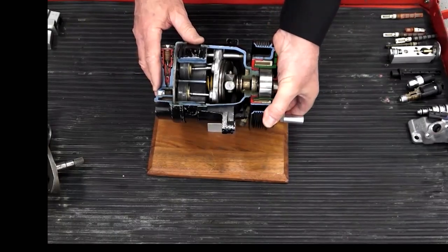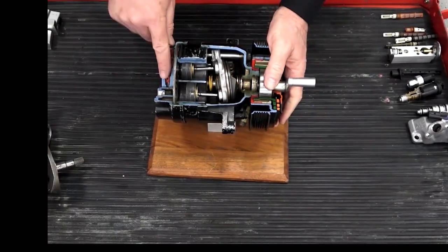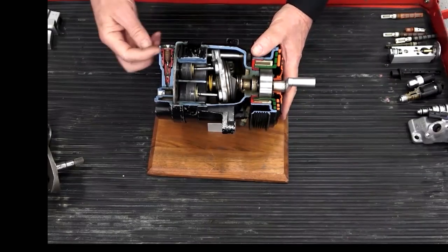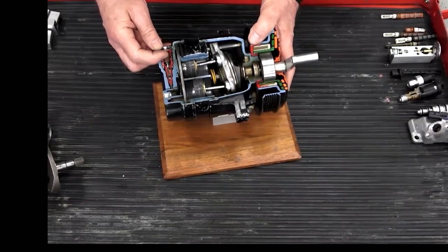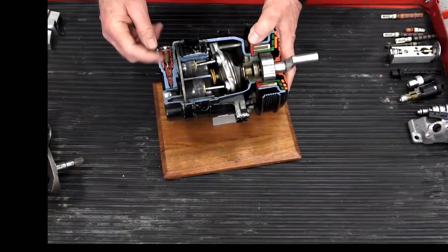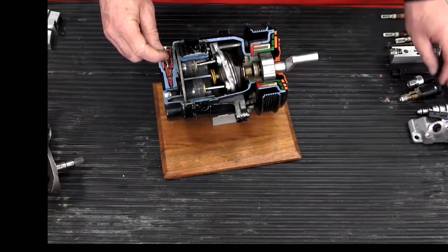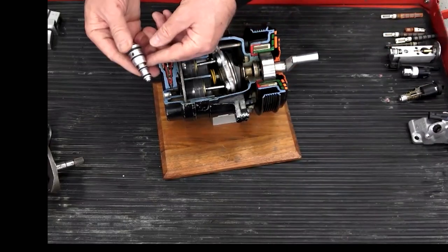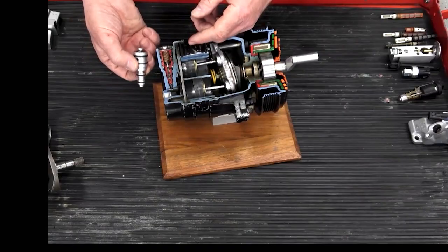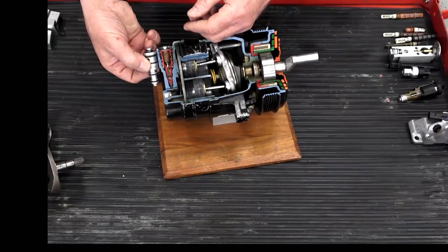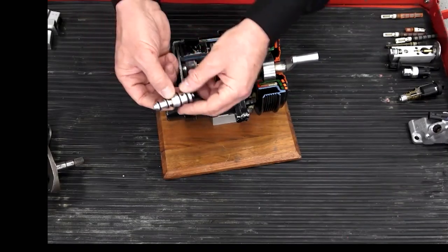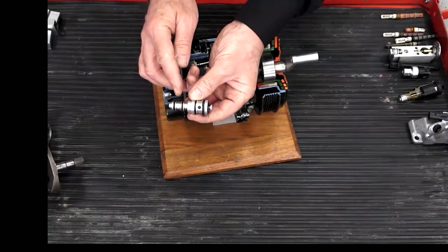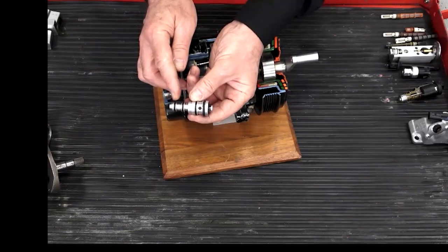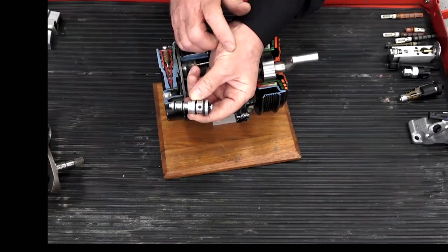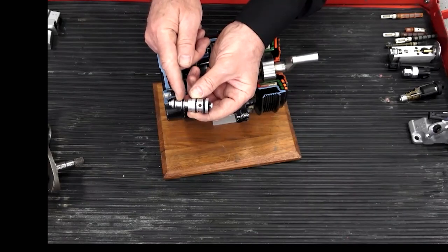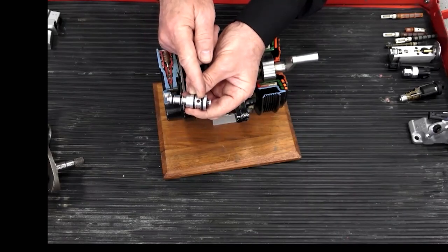So the way this works is this. If you look in the rear head here, there is a control valve. If you look closely, you can see an actual pneumatic bellows in the rear head. And this is a control valve from this exact compressor. If we look closely at the valve, you will see there are three areas. There are four O-rings, one here, here, here, and here. And there's a section here, a section here, and a separate section here.